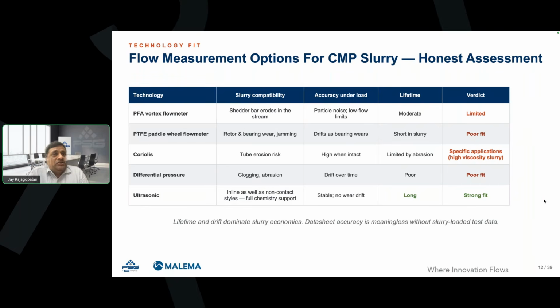Ultrasonic is definitely a strong fit. There are two types of ultrasonic flow measuring technologies. One is clamp on. The other one is inline, though even though it is inline, the actual electronics and the sensing mechanism are externally mounted to the flow tube itself. So hence, pretty much no obstruction. It's very stable and very repeatable. It's an extremely strong fit. If you notice, for almost all CMP tools currently being manufactured, the first choice is ultrasonic, and the second choice is Coriolis because of the high viscosity applications.